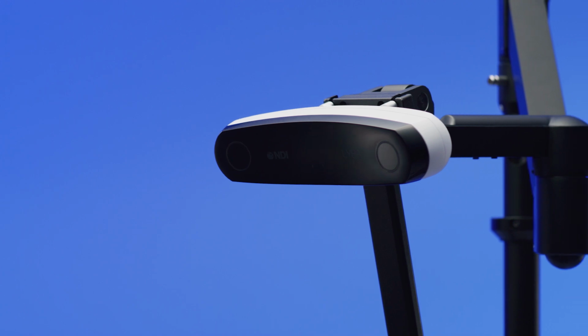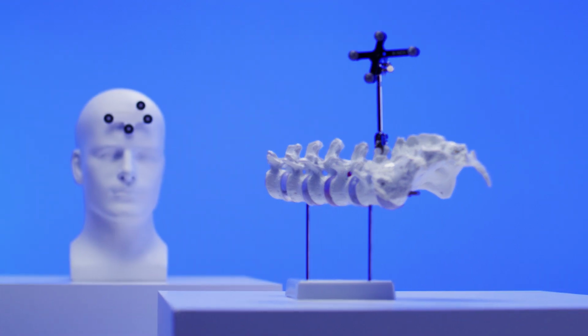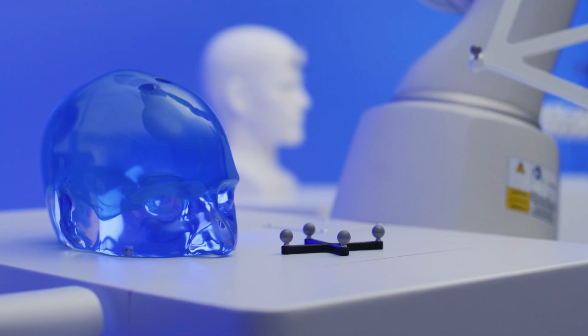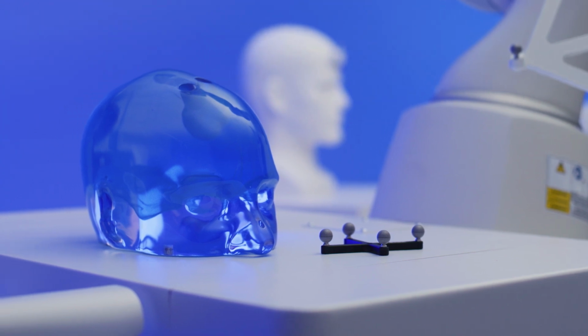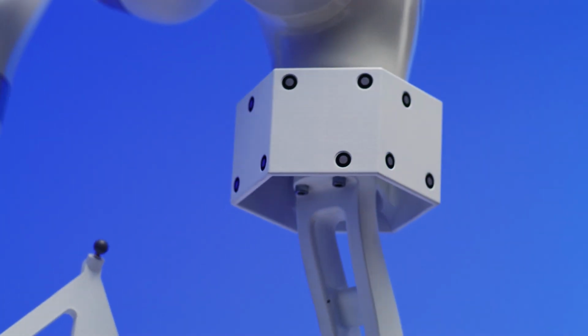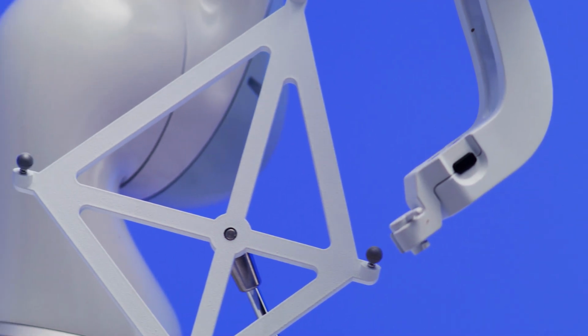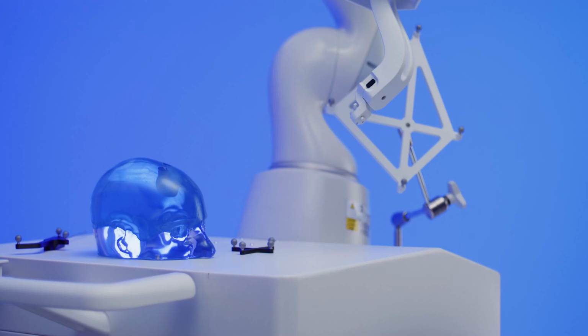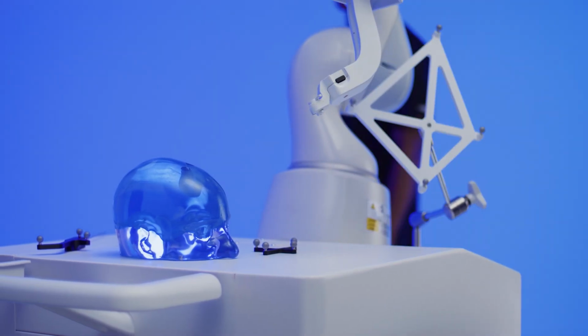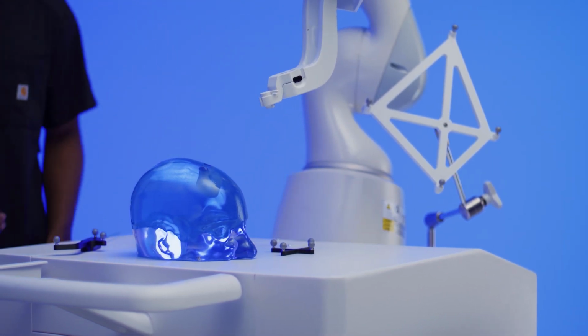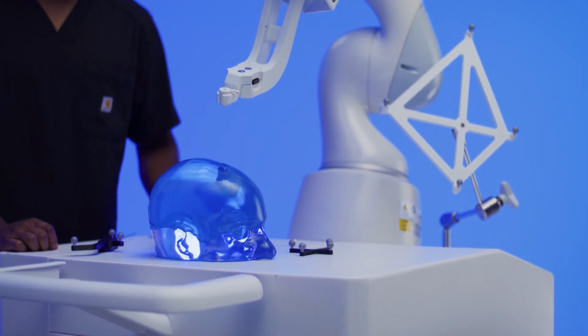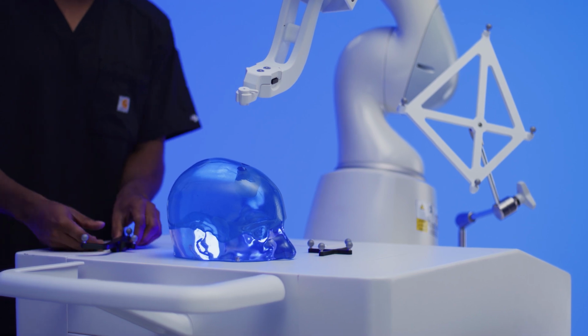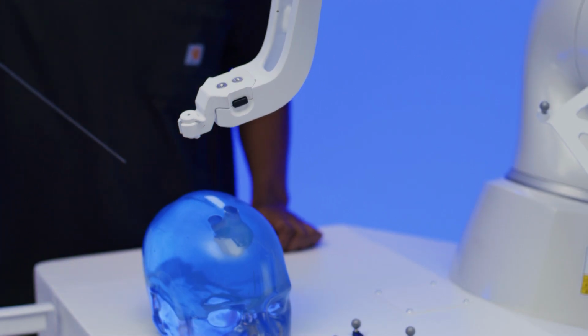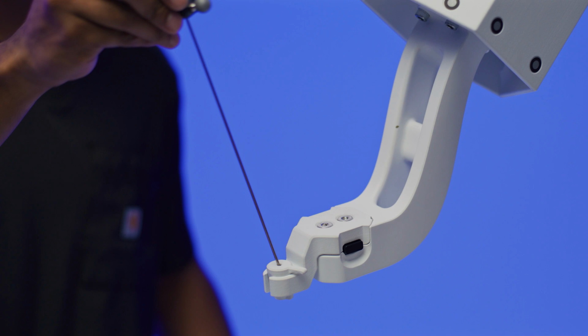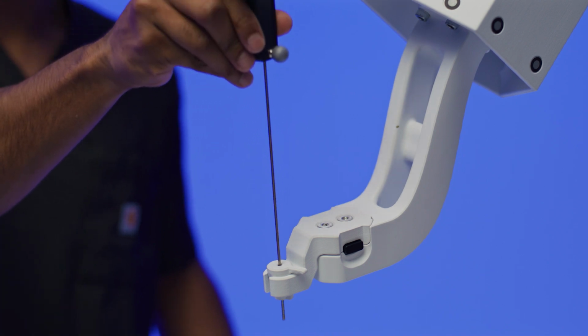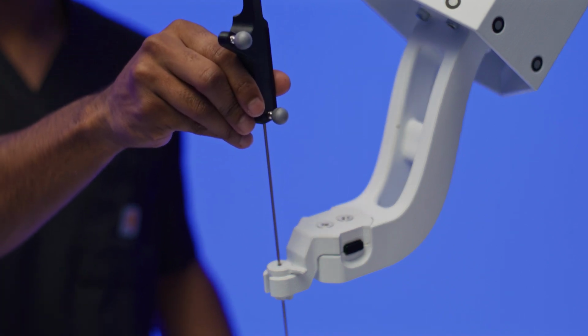demanding OEM applications. For spinal, TMS, and cranial procedures, where operative space is limited, the optical tracker complements the workflow of most OEM applications. With its ability to track 6D tool positions and orientations with sub-millimeter measurement accuracy and repeatability, the Polaris Lyra delivers exceptional tool tracking performance. The Polaris Lyra supports passive, active wire, and active wireless tool types.